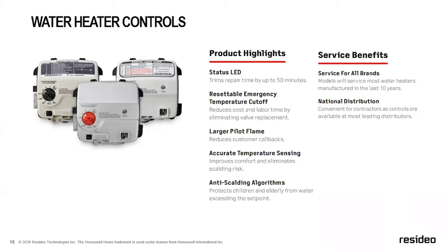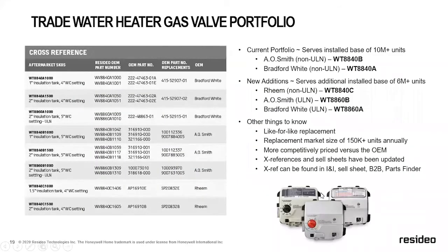As you can see, we have 3 different models there which have some similarities, but the idea behind these 3 different models is that depending on which major brand you're replacing, we have a model that is going to be a direct replacement for the OEM control that comes off the water heater. So we look at this chart here, and the major manufacturers, which happen to be A.O. Smith, Bradford, and Rheem, all 3 of them are covered by these water heater controls. All you have to know is either the OEM part number, which is marked on the gas control that you're removing, or, if you don't have that, you go by the insulation of the tank. Depending on the depth of the insulation, you can have a longer or shorter gas valve insert. Okay, like for like replacement.